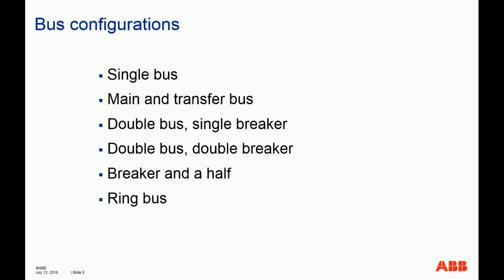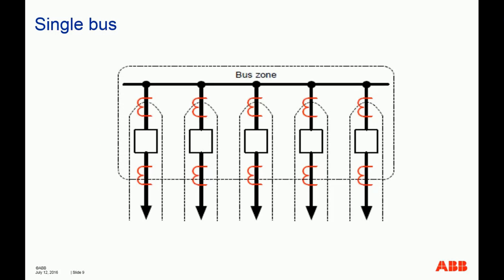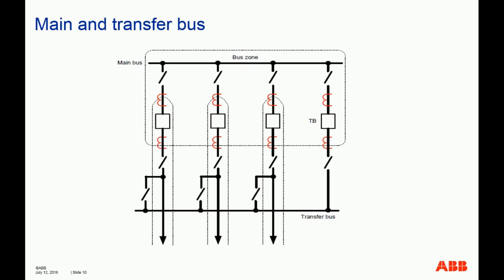Next, we are going to look at some different types of bus configurations. First is the single bus. Single bus is typically used for smaller stations, and sometimes you will still see that nowadays. The next is the main and transfer buses. The advantage of this type of bus configuration is that any of these four breakers you see here can be taken out of service for maintenance, for repair, or whatnot.